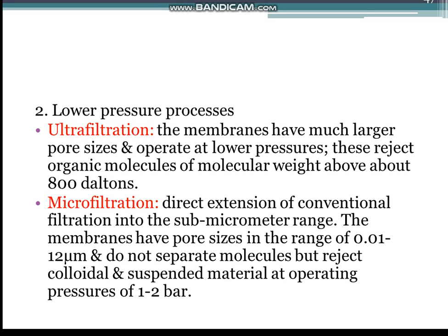Microfiltration membranes have pore sizes typically in the range of 0.01 to 12 micrometers and do not separate molecules but reject colloidal and suspended material at operating pressures of 1 to 2 bar. Microfiltration is capable of sieving out particles greater than 0.05 micrometers. It has been used for water treatment in combination with coagulation or PAC to remove particulates and some dissolved organic carbon prior to the reverse osmosis membrane and to improve permeate flux.